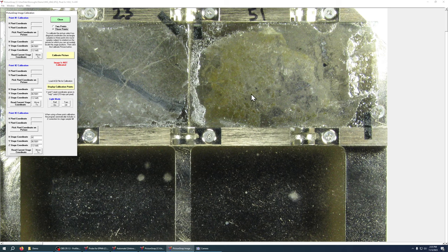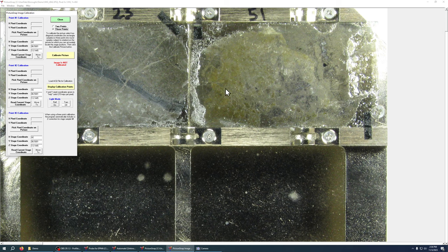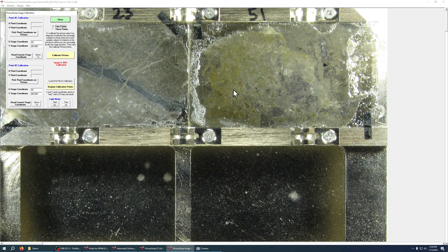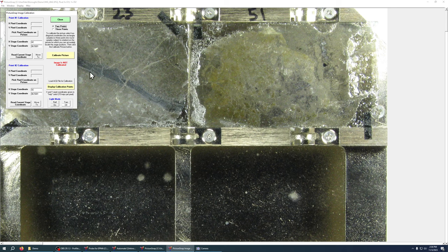Obviously that only works if it's got a planar flat tilt to it where irregular sample surfaces can't account for that. Since we're doing the whole holder we're going to do a two point calibration since these samples will have different heights anyway and maintaining the z-axis distance is going to be impossible.